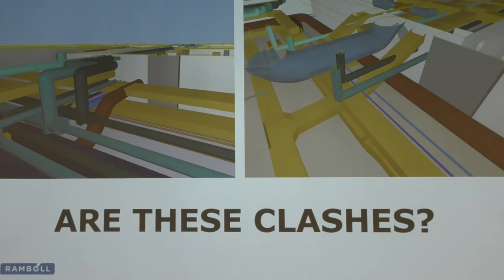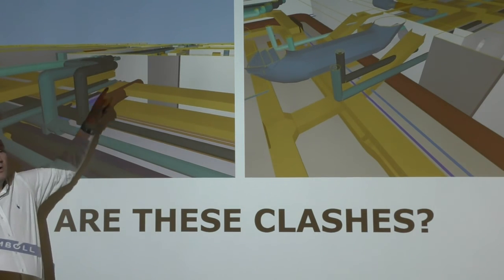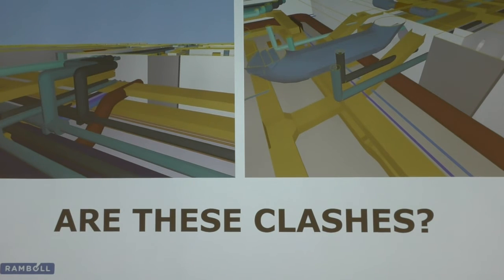So the argument that Dave is coming up with is, and luckily this job isn't in the UK, it's somewhere else but I won't tell you where, that if you've got to do a fire compartment between that and that pipe, you need to make sure there's a 200 mil gap between the edge of the fire barrier for the containment and the edge of the fire barrier for the pipe, because they're only certified in 200 mil. It's not my area of expertise, so I wouldn't like to talk about it technically. But from a consultant's perspective, producing a technical design, you can of course incorporate that.